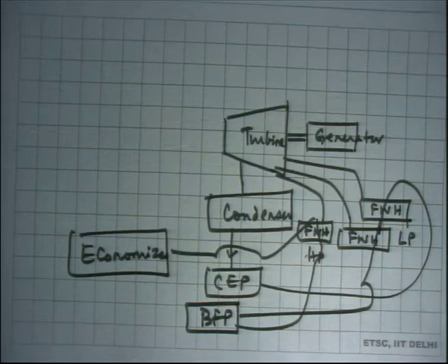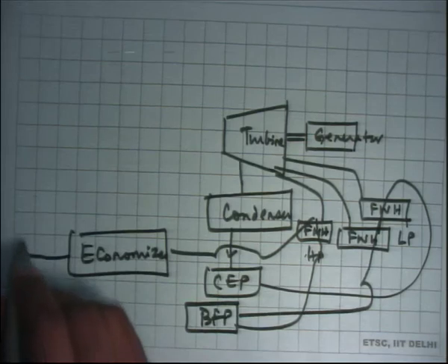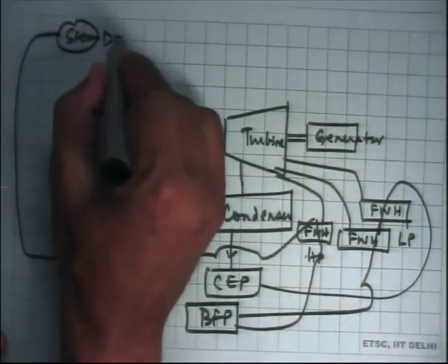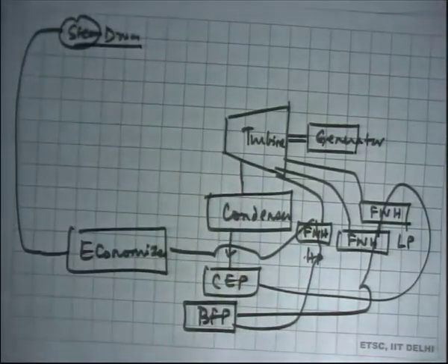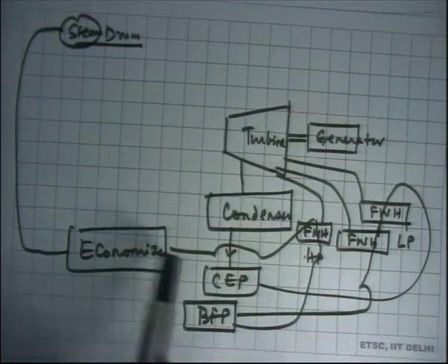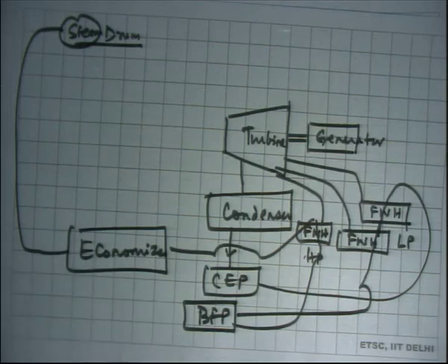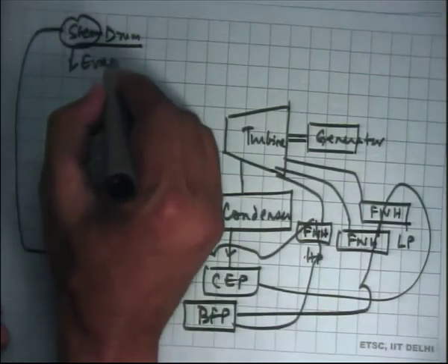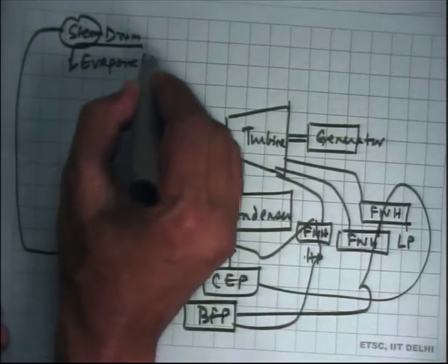Okay. From the boiler, the flue gases, just before they go out, they go through the economizer. Okay. So, then after the economizer the water goes to the steam drum, which is what you saw at the top floor of the boiler. Those of you who climbed the boiler, at the top floor of the boiler you saw the steam drum. Okay. So, the economizer water is taken to the drum, and from there it goes to the evaporator in a cycle.